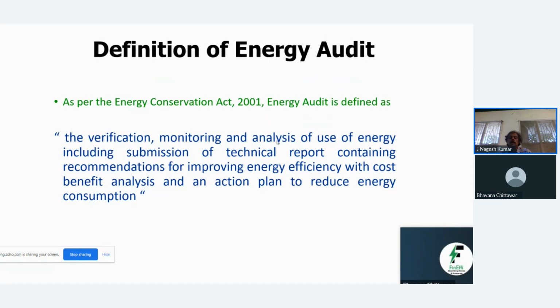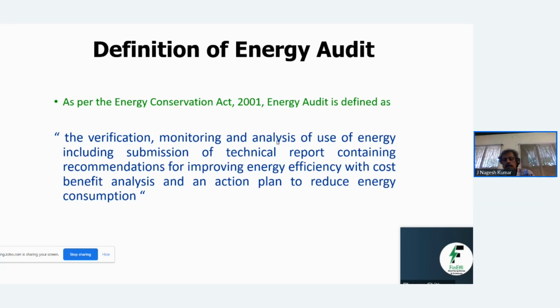For example, in one industry we saw about 10 compressors being used, with pipelines of more than 2 kilometers running all over towards a place, for not a very heavy job, just a light turning activity where screws had to be inserted into some coaches. The torque requirement was very low, yet air was being used, and leakages were up to 35%. So we looked at this, and we saw the compressors already had VFDs, some had soft starters. Every possible thing that could be done on the compressor side had already been done.